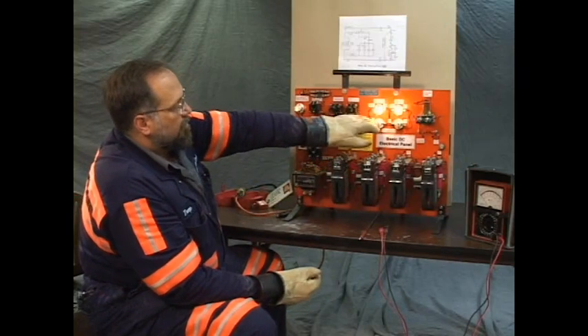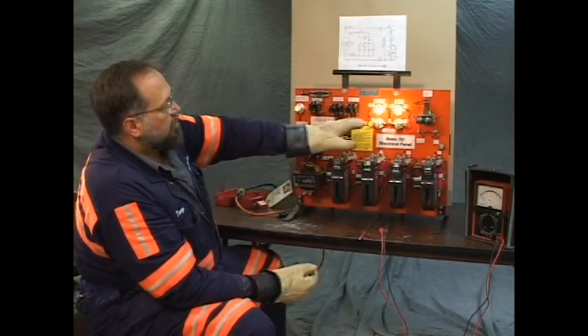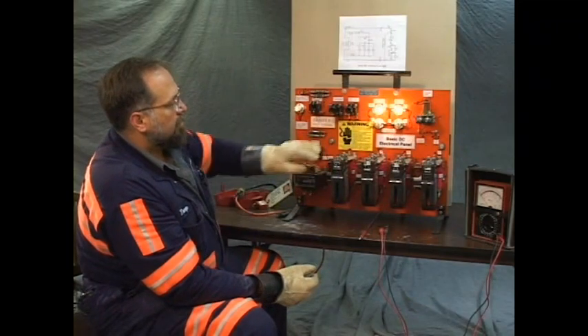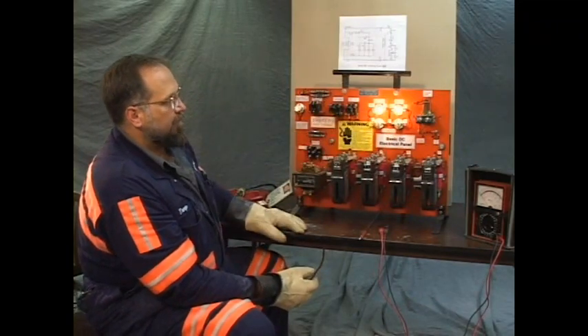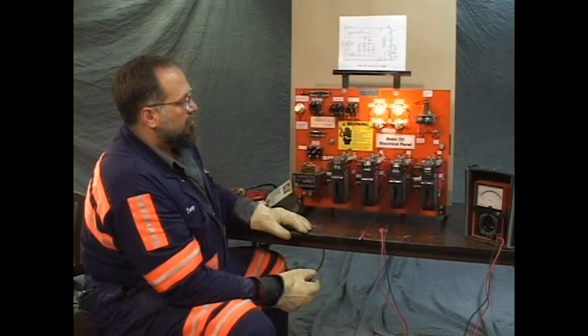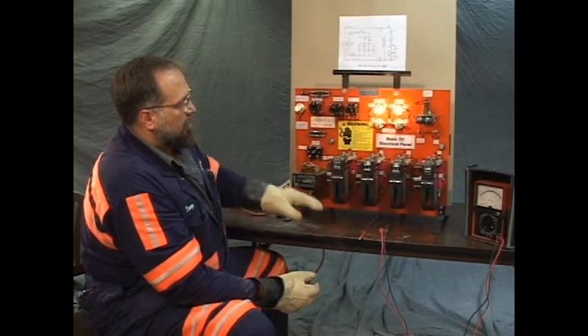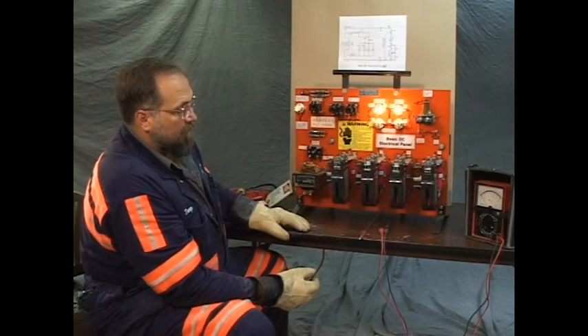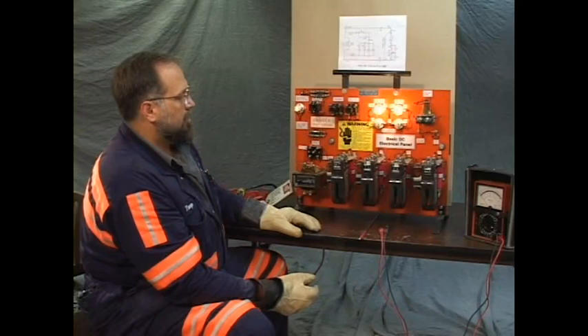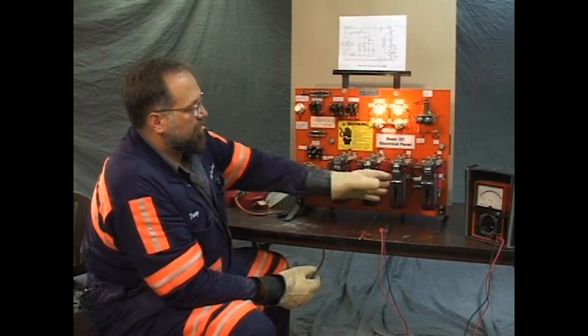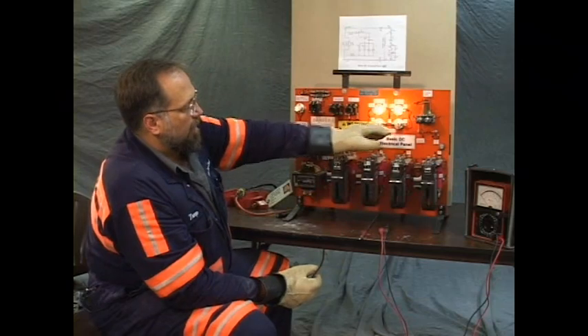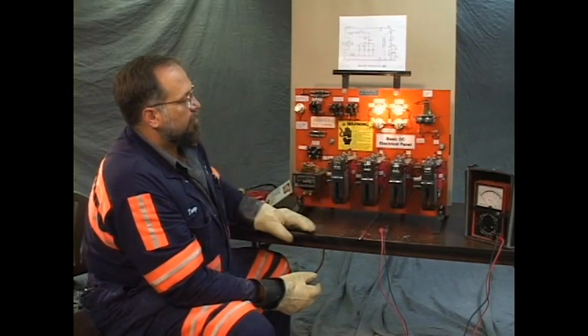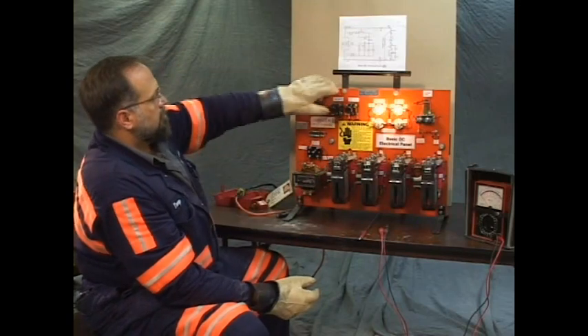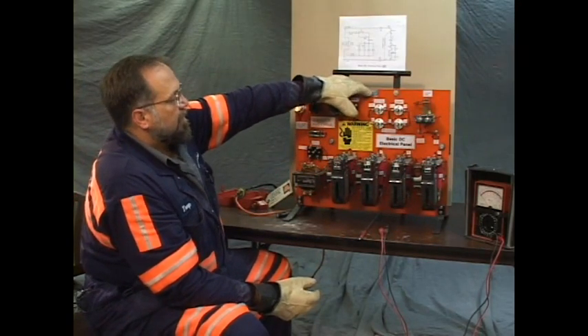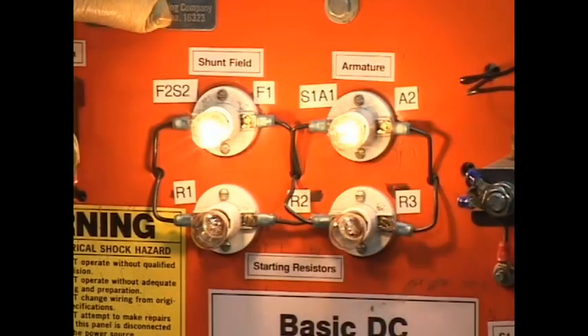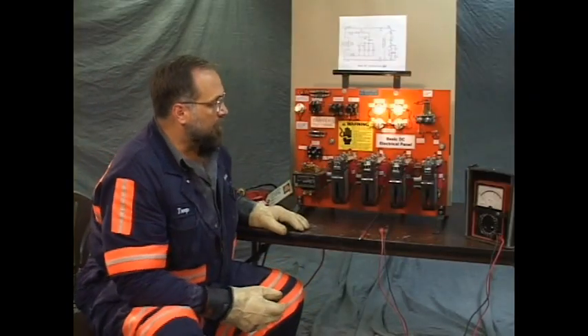The effect of that with the power lights, the indicator lights: when first energized, the shunt field light is very bright. These 2 resistor lights on the bottom are dim, and the armature light is dim. After the 1A contactor closes, the bottom left resistor light goes out. The other 2 become brighter. After the 2A contactor closes, the bottom right light goes out, and this light is very bright for the armature. Watch the lights and listen to the contactors. We'll try it one more time. There you have it. That's correct operation.